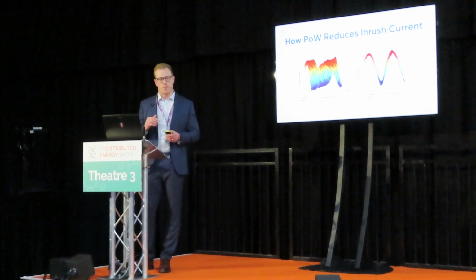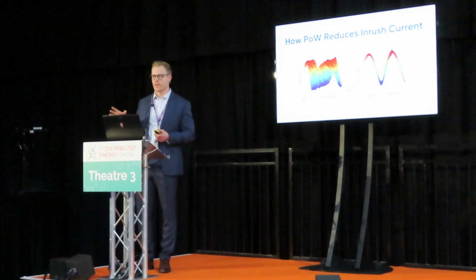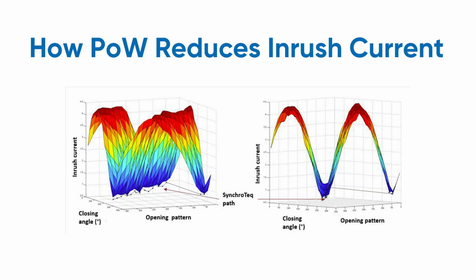So how does point-on-wave work? As we just discussed about transformer saturation, when you open a transformer, when you de-energize a transformer, there is a residual flux left in the transformer core. The transformer is an electrical magnetic component. The core is magnetic and has lots of particles that rotate when the transformer is energized. When the transformer is de-energized, all of these particles stop rotating and they all point in one direction. That's the residual flux. It's the magnetic polarization of the core.